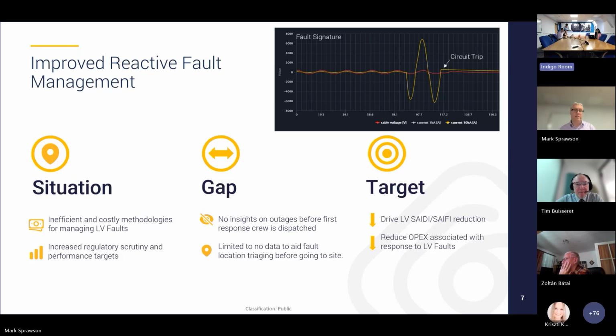The simple diagram at the top right shows nice sinusoidal waveforms, then a huge spike—in this case around 7,000 amps—which causes the circuit to trip. This is a waveform captured from the grid edge intelligent device. You might ask, how does that actually help me day-to-day? I'll show that in a second.